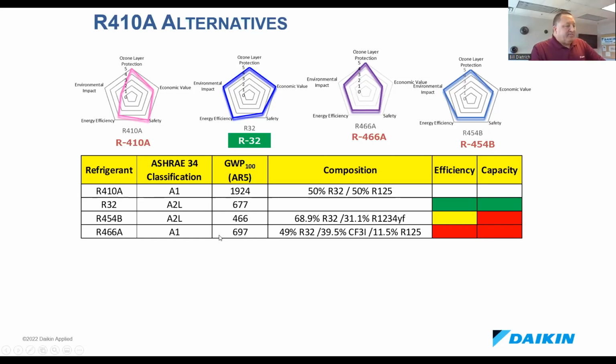the market. So the key alternatives we're going to see going forward are the R32, which, just in disclosure, Daikin has used quite a bit globally. And you can see it's an A2L. It's got a GWP of 677, so it's not great, but it's below the 750 regulatory thresholds we're seeing. The nice advantage of it is you get actually more efficiency and more capacity than you got with 410A.